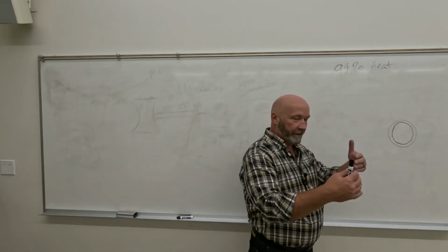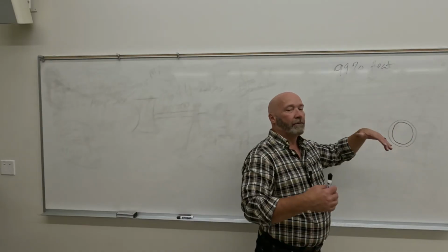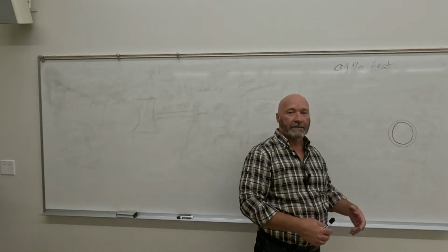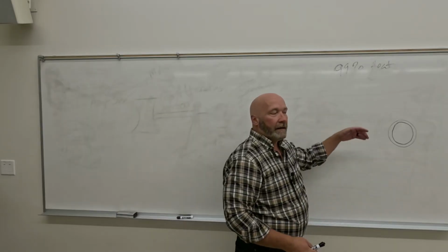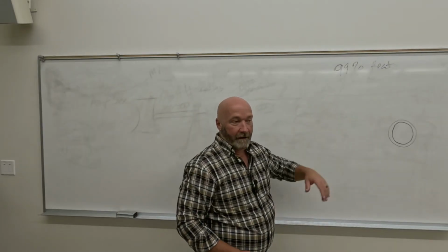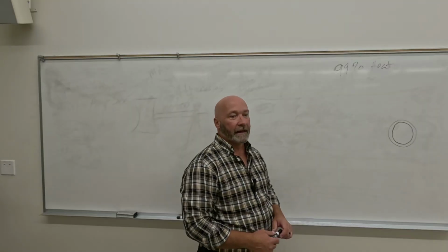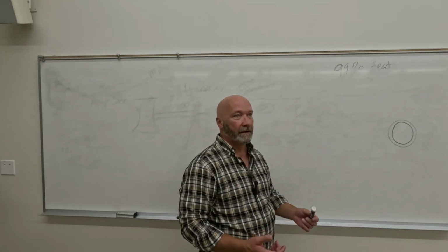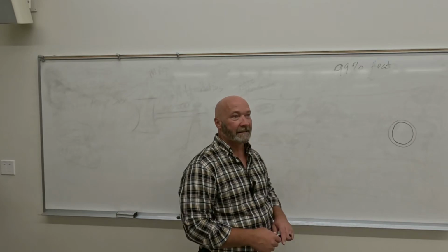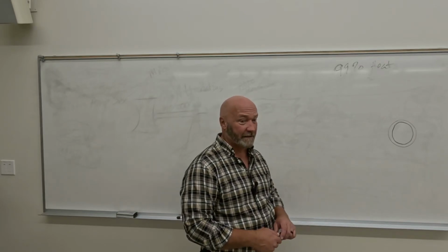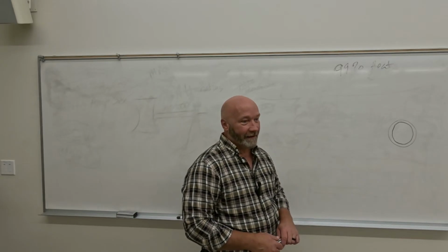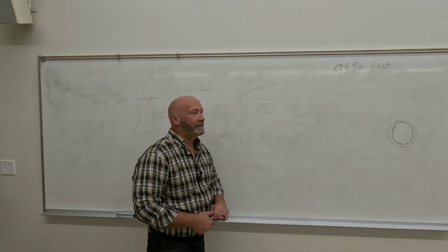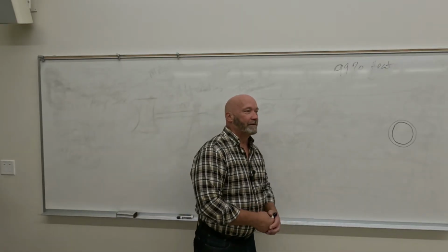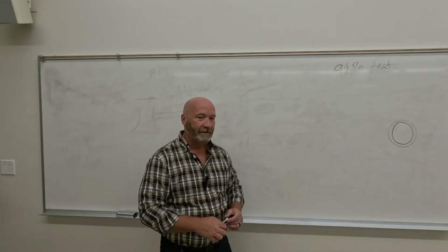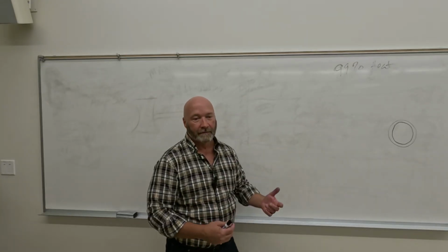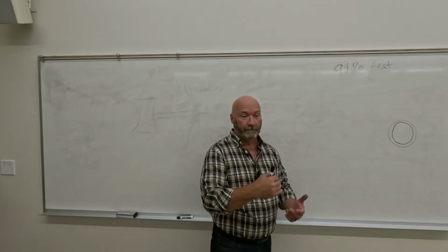You create heat on the filament. You deposit the heat there. You create more heat as the electrons go back into the circuit. You got heat, heat, heat. How hot does it get? Well, you can melt the anode, but the melting point of tungsten is like 3,700 degrees Celsius. That's a lot. So by melt, you're going to etch it some. You're not going to just completely melt it, but it's enough that it will put some damage on it.